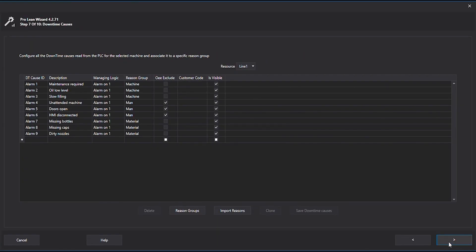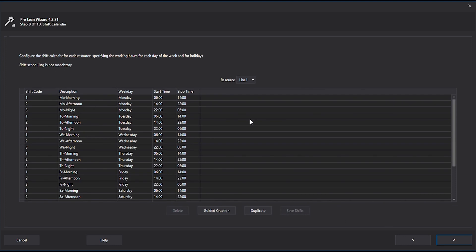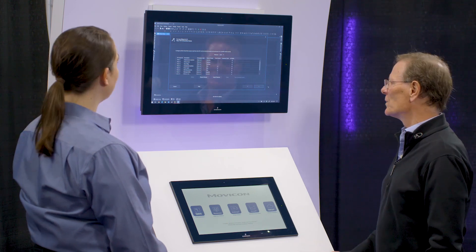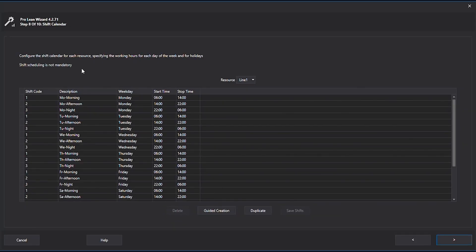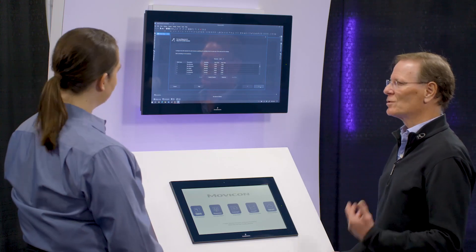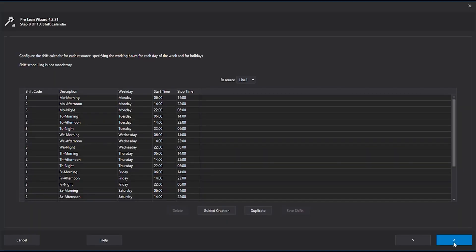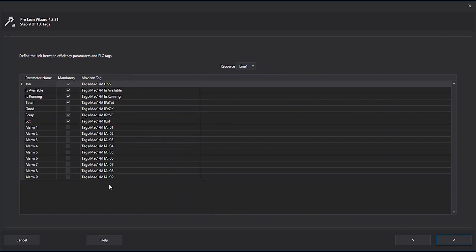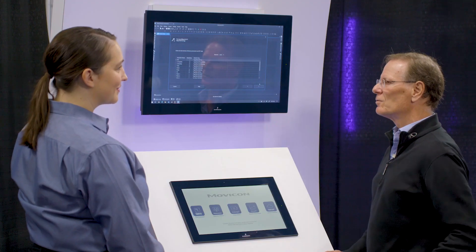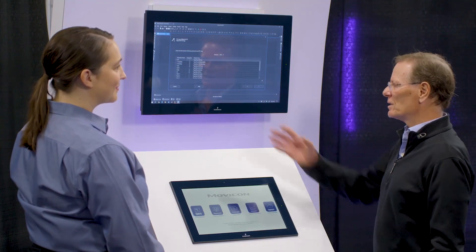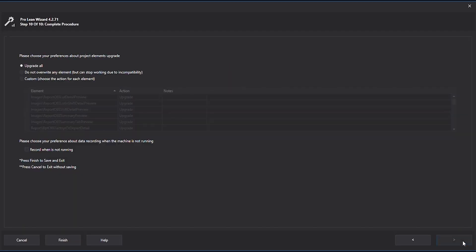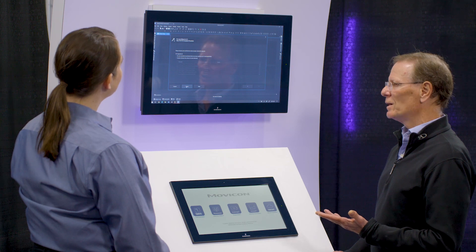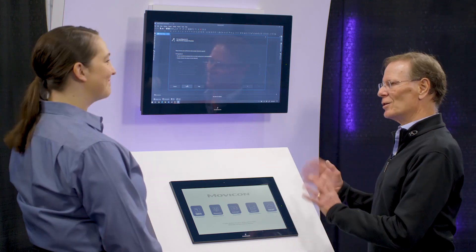Then I go to creating downtime reasons — that's really important. When downtime occurs, why did it occur? I can produce a top 10 report of reasons for downtime, and process engineers can address those one at a time to improve overall equipment effectiveness. The next step is creating shifts — it's all about downtime during planned production time. Then a screen with just 11 tags: when a part was produced, how many parts, was it scrapped, and when an alarm causes downtime. I hit the finish button and everything I showed you is set up — just like that.